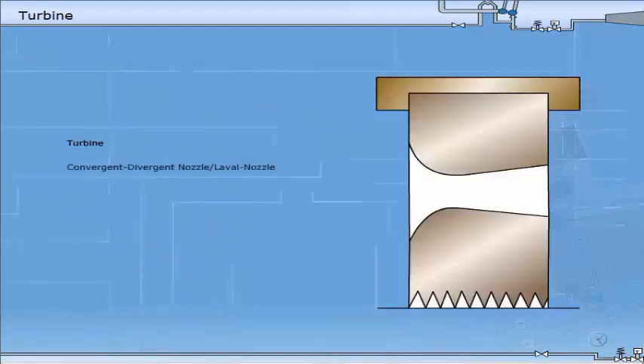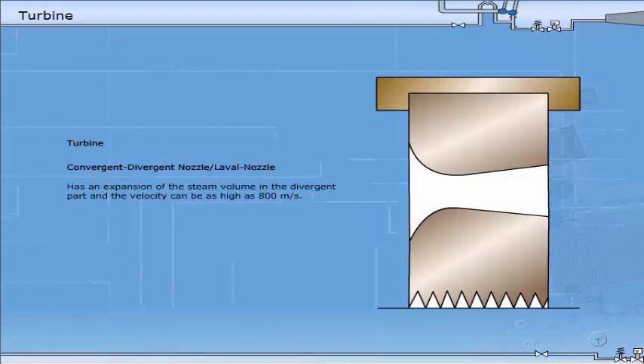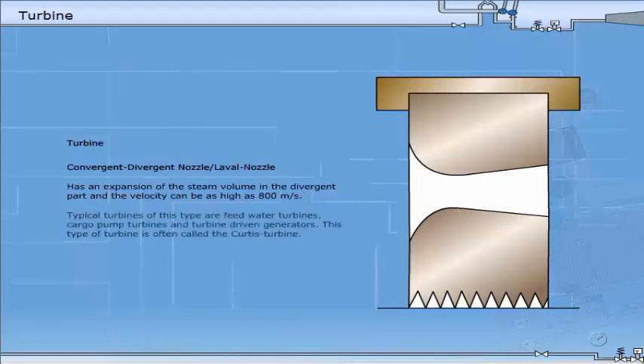The convergent-divergent type of nozzle, also called the Laval nozzle, has an expansion of the steam volume in the divergent part and the velocity can be as high as 800 meters per second. Typical turbines of this type are feed water turbines, cargo pump turbines, and turbine-driven generators. This type of turbine is often called the Curtis turbine.